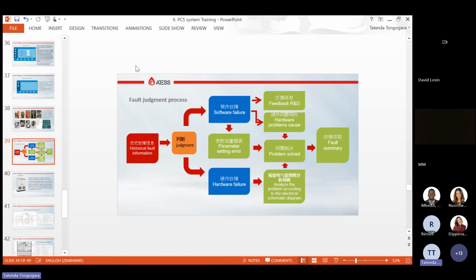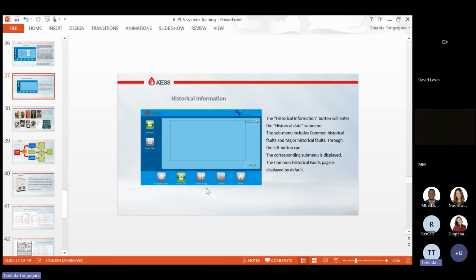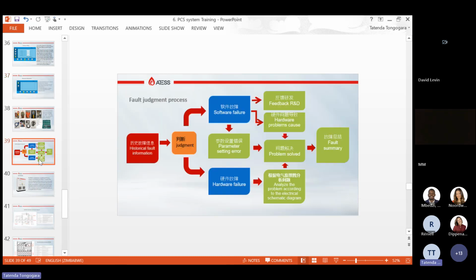So when troubleshooting your system, you have your historical data. On the history information, that's where you see the faults. It could be a phase sequence fault, overload fault, overcurrent fault. This is where you see your fault pages. So when you're troubleshooting, the first thing that we ask is your historical information. We check, is it a software failure, a parameter setting error, or a hardware failure. On this one, we help you do the troubleshooting.